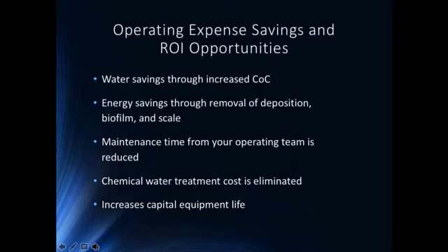Go ahead, Marie. Yeah. Operating expense savings and ROI opportunities. Again, we talked about water savings through increased cycles of concentration, energy savings. Another big thing is maintenance time. If you're like most of the people that I deal with, within the last 3 to 10 years, you're probably getting by with a much smaller maintenance staff than you used to. And unfortunately, there's just as much work that needs to be done. And so anything we can do to reduce the amount of time that your maintenance and operations staff have to spend taking care of the cooling tower is beneficial. Things like meeting chemical deliveries, or reducing the number of tests they need to run, or reducing the amount of maintenance that needs to be done to the cooling tower from a cleaning standpoint, allows them to do other things that can have more bang for the buck. Obviously, chemical water treatment cost is eliminated because the chemicals are gone, and it increases capital equipment life.